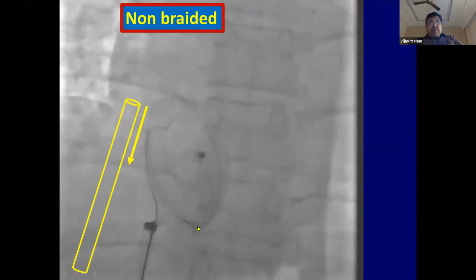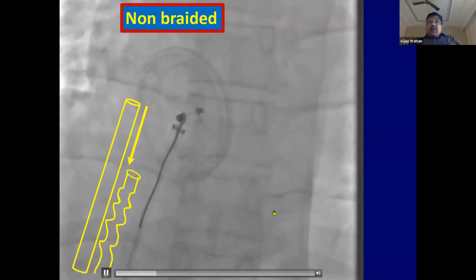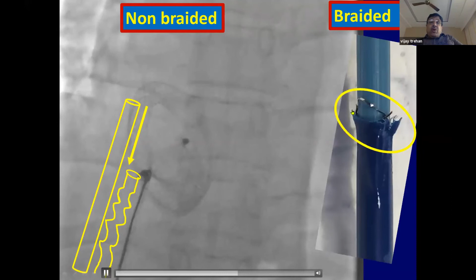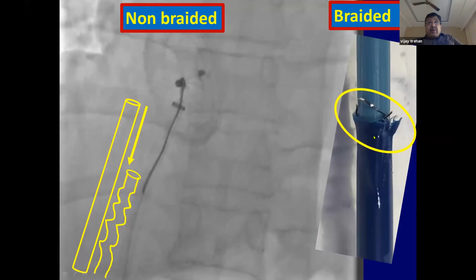So even if you're able to get your pin into the sheath, now the device will not move within this kinked sheath. So one should refrain from applying this much brute force, because even if you're able to get a device partly into it, subsequent movement will be prevented because of this distortion of the sheath. In this case, we had already consumed the non-braided sheath, and we had the braided sheath, and on a braided sheath you cannot cut a bevel. So we were limited.